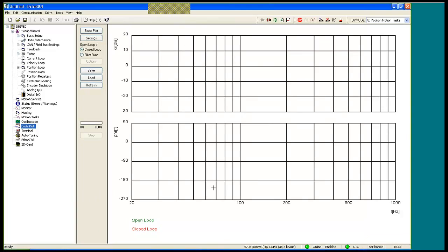Okay, Bode Plot. The screen gives us the ability to perform a Bode test to check the bandwidth performance of the system along with phase margin. So gain and phase margin test to see how well it's performing or how to look for the problems that may be occurring with mechanical axis that the servo's driving. And it would assist us in helping select filters to maybe attenuate frequency issues that exist. The Bode gives us an inside look at what the problems are for resonance and performance of the servo system.